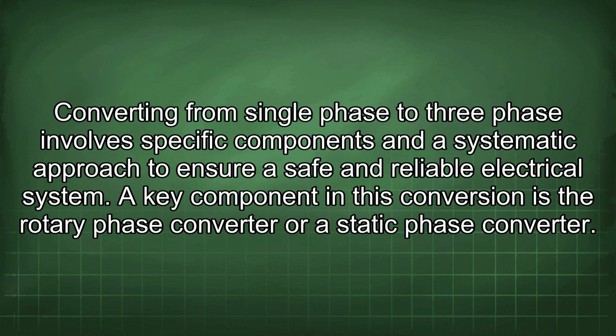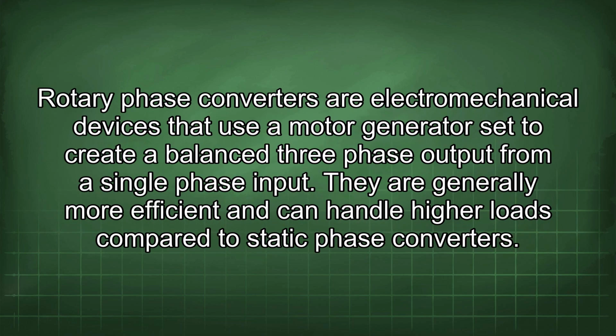reliable electrical system. A key component in this conversion is the rotary phase converter or a static phase converter. Rotary phase converters are electromechanical devices that use a motor generator set to create a balanced three-phase output from a single-phase input. They are generally more efficient and can handle higher loads compared to static phase converters.